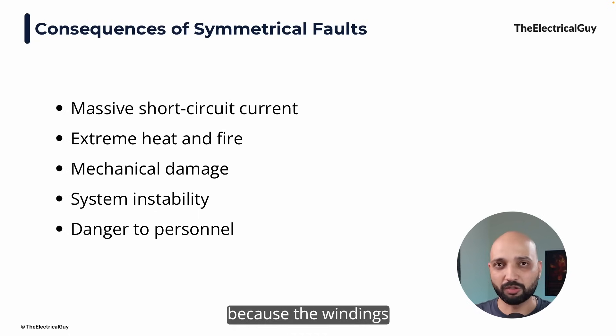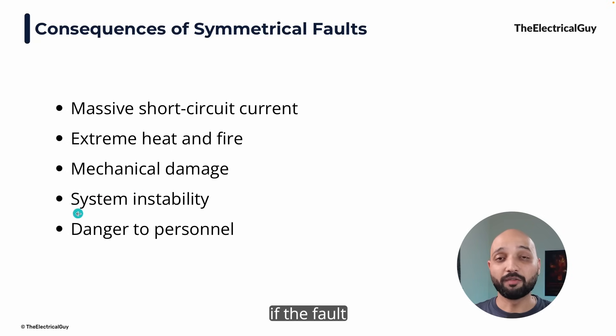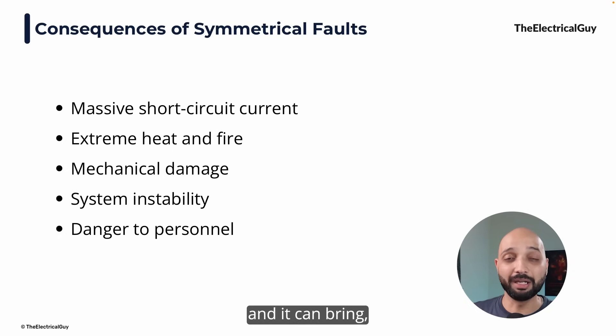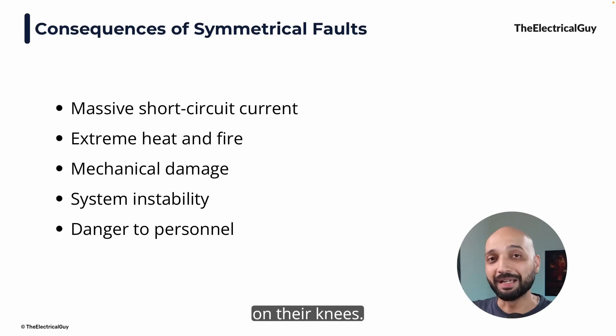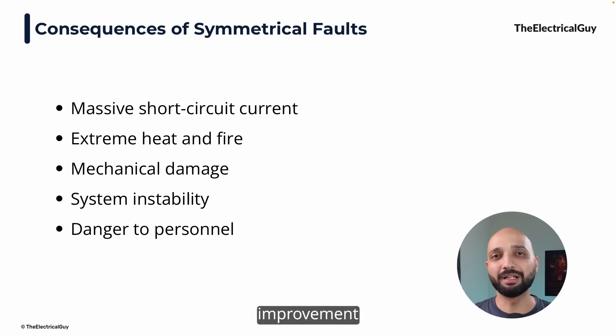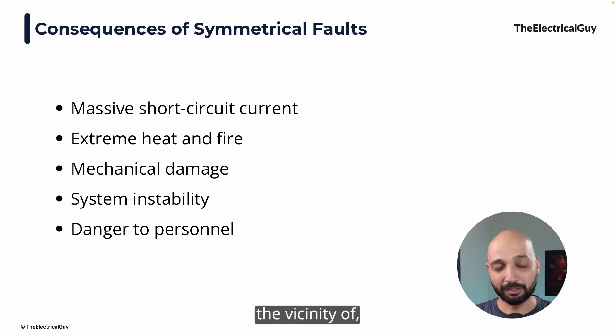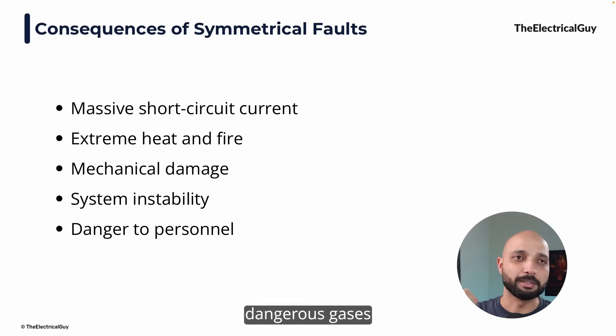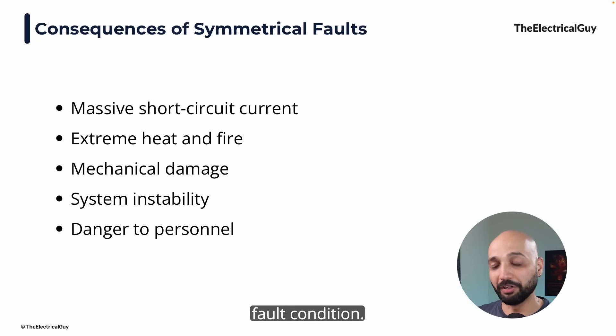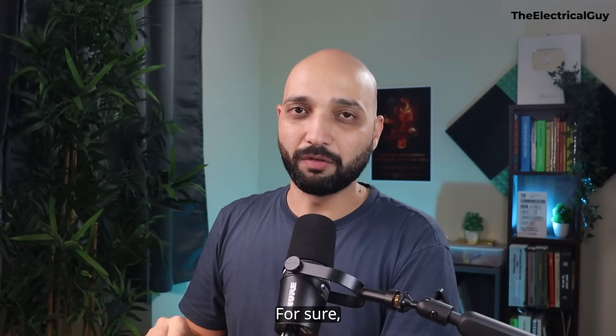The electromagnetic forces can damage generators and transformers, because the windings will experience a lot of force. Of course, if the fault is not cleared in time, it may cascade and create complete instability in the system, bringing even the strongest power system to its knees. Thanks to advanced protective systems and improvements in circuit breakers, these faults can be tackled. It can also create danger to personnel — if persons are working in the vicinity of the fault, it can create a flash, dangerous gases, and many other hazards.